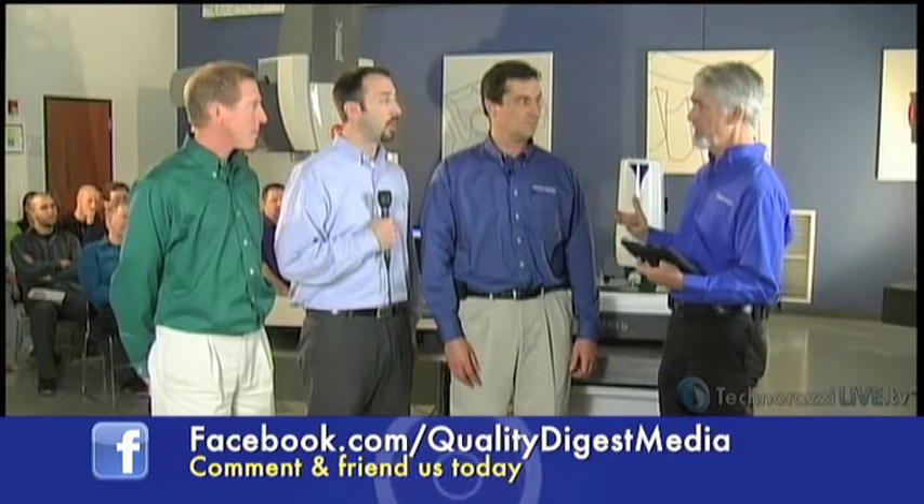We already touched on calibration — just because you move this machine from one location to another doesn't necessarily mean you'll have to immediately recalibrate. You'll want to do a qualification routine, but not necessarily remap the entire thing. The qualifications are a one to two minute process. So you're going to do your normal calibration schedule for the whole machine, which might be once a year.